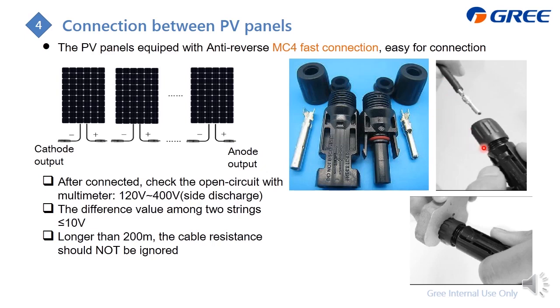After you connect it, please check the open circuit with a multimeter. The voltage should be within this range for one string, and the difference between two strings should be less than 10 volts. If the wire is longer than 200 meters, please consider the resistance.